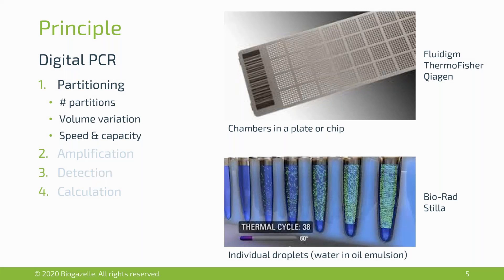One of the basic principles is that the bulk reaction to which you apply a PCR reaction is being separated into different partitions. There are two different types of approaches: either a plate or chip-based structure that creates a physical separation in a typically 2D structure — examples include instruments from Fluidigm, Thermo Fisher, or Qiagen — or alternatively, a water-in-oil emulsion is generated, producing thousands if not tens of thousands of droplets.